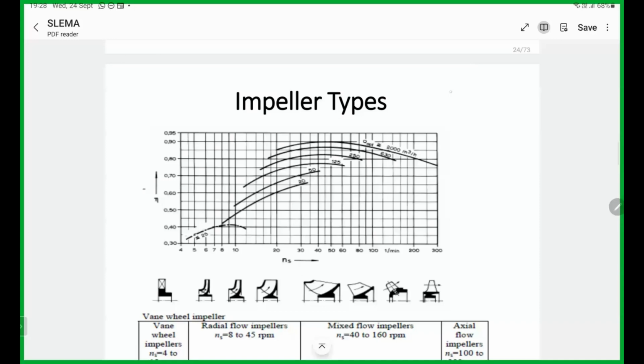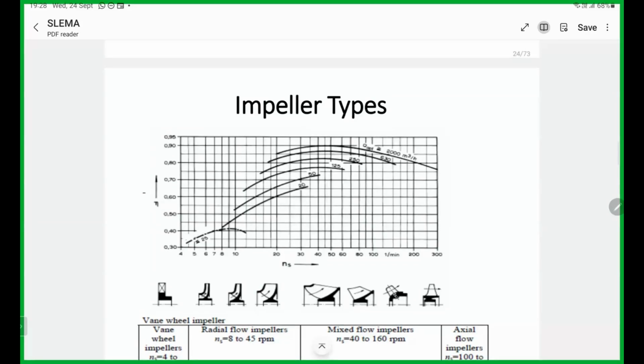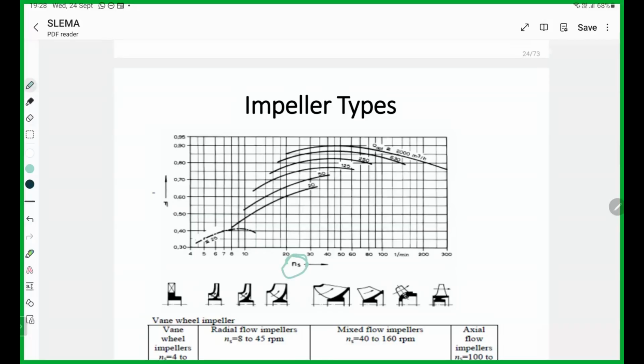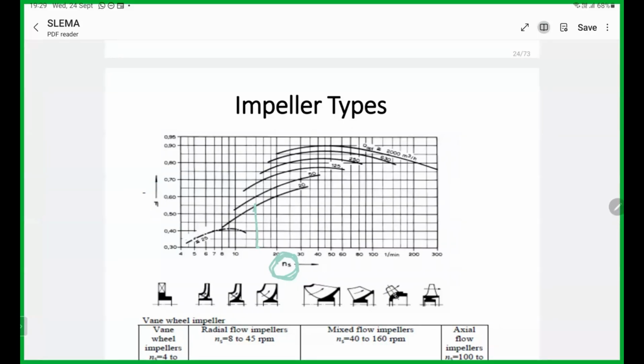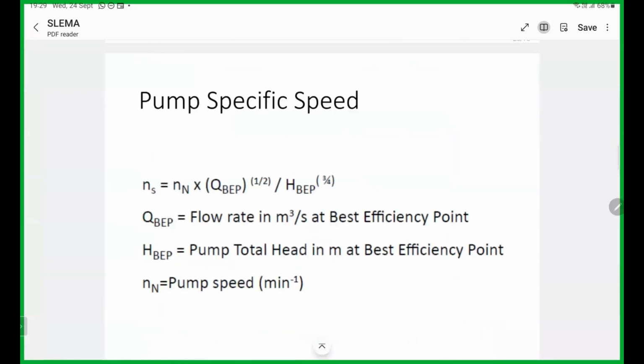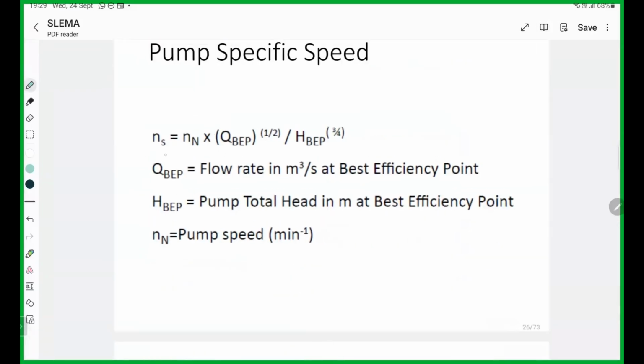Then if you come to the impeller types, the important thing is this Ns, specific speed, that you can see here. Depending on the specific speed, the pump efficiency is there. You have to select the correct specific speed for your application. Then only can you select the most efficient pump, right? The important thing is specific speed. The specific speed equation is this: Ns equals RPM, flow rate, head, right?